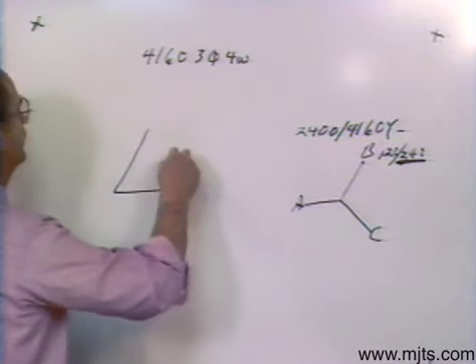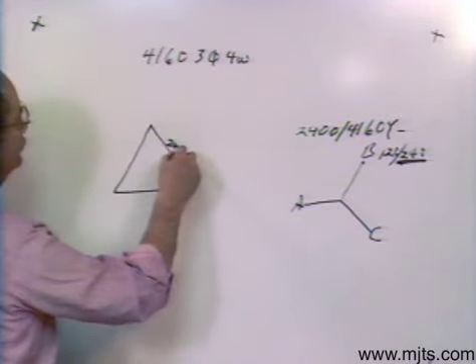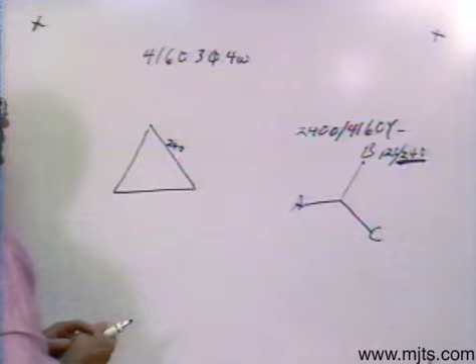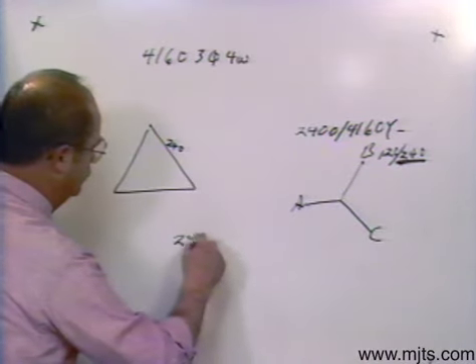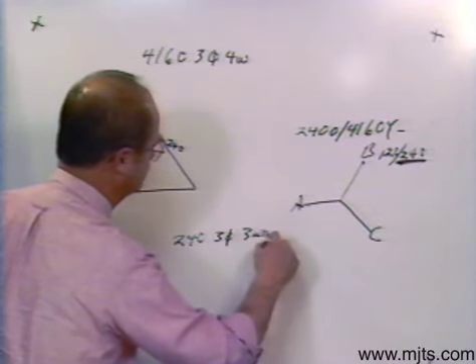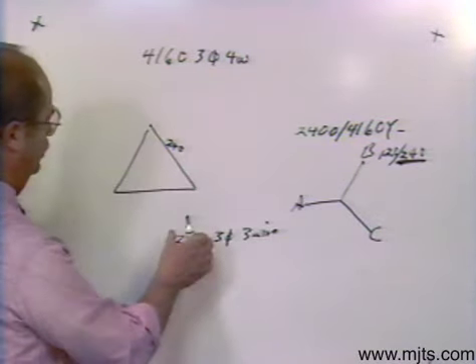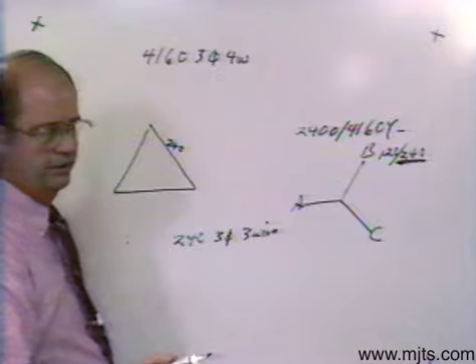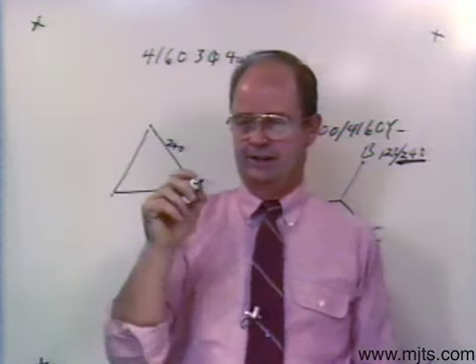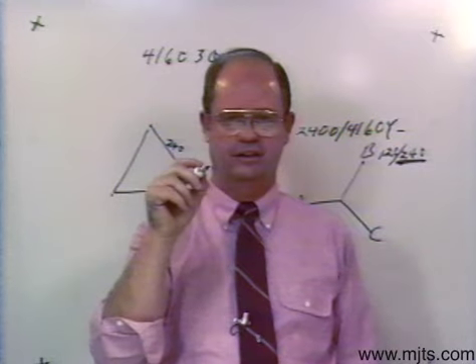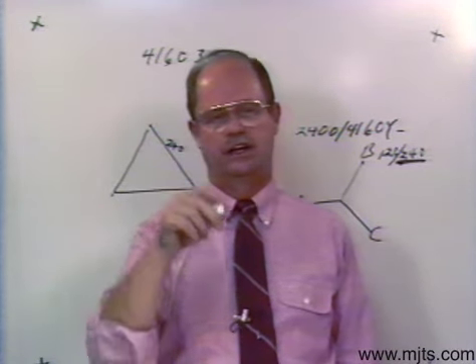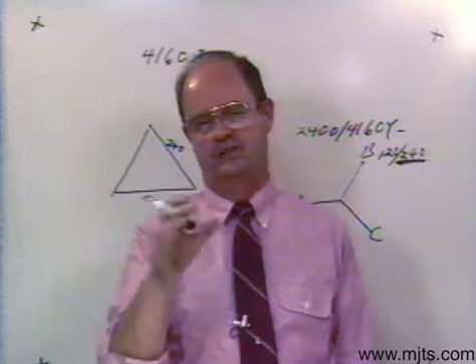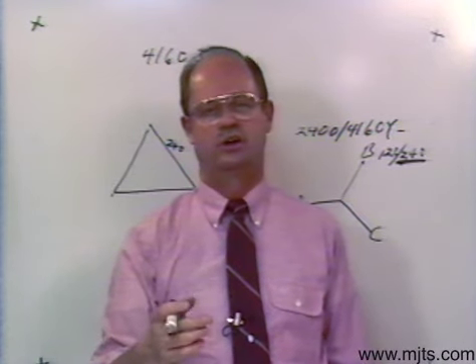Let me go through the delta connections and show you what possibilities are available on the 240 or 120/240. If I know that I want a delta connection and I draw a delta diagram, and my tubs are each rated at 240 volt, then between my phases all the way around I'm going to get 240 volts. If I wanted 240, 3-phase, 3-wire — no lighting load, just power load — then I take one of my corners, it doesn't make any difference which one. On the diagrams, C and neutral are one and the same, but any phase can be grounded.